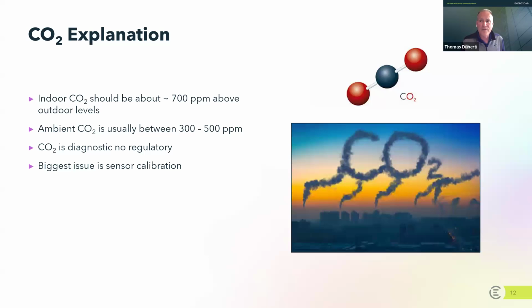We want quality air for the occupants in our spaces. Again, the outside standard is around 400. Usually you want to keep it under 1,000. But the main thing is if your buildings have CO2 monitors, and if the mechanical systems are being controlled at a certain level of CO2, you really have to get in there and understand it to make sure that you are not having waste occur in your buildings as a result of these failing or miscalibrated systems.